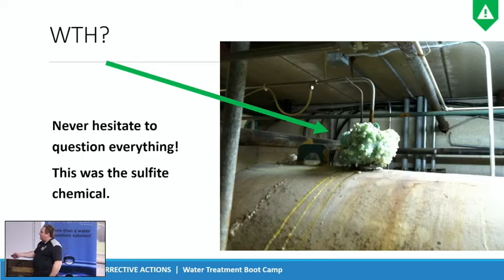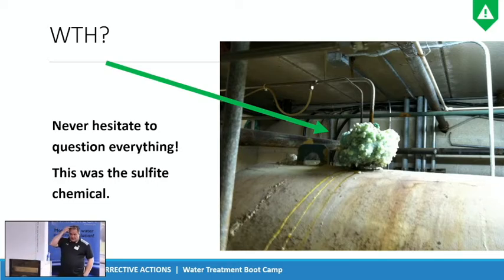I don't remember if this is a feedwater tank or a deaerator. But the other thing is that's your chemistry, right? And what's the other thing I told you this morning about where the sulfite should be injected? Into the water. If I remember correctly, this isn't my customer, but I thought someone told me that this just goes right in here and runs right through that air column. So there could be a tube in there. Maybe they took the extra effort and ran a tube all the way down into the water, that's fine. But something's leaking.